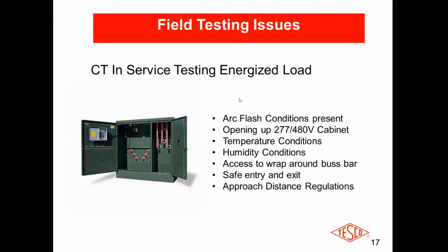So, an alternative CT testing with a de-energized load. This came up a few years back when I was at a meter conference. We covered a range of topics, and I was talking about CT ratio testing, meter testing, and burden testing we were doing. We got into a discussion, and it turned out this particular company had made an alternative decision - rather than using the suits, to enforce a disconnect notice on the customer and advise them of what they're planning to do.